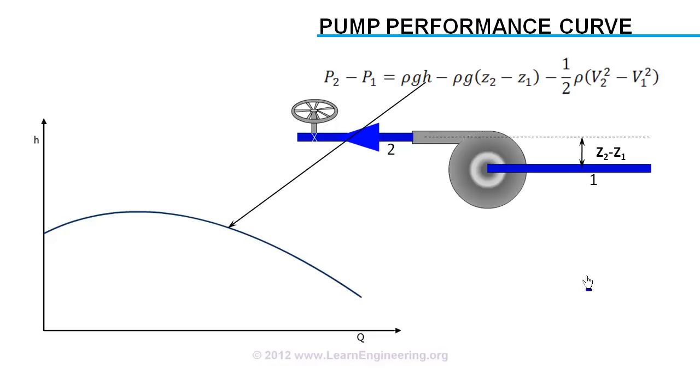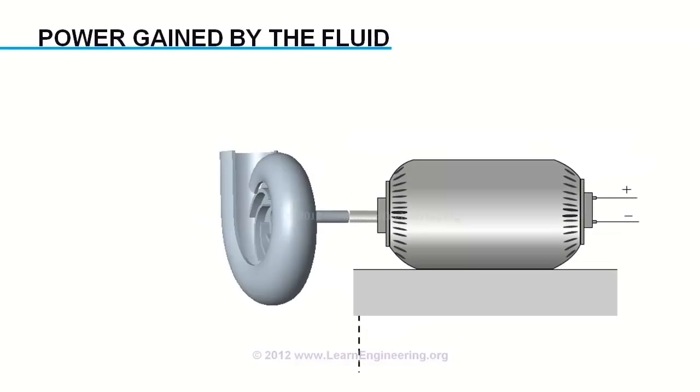Now, we will see how much power fluid is gaining from pump power input, or shaft power. Power gained by the fluid will be lower than the power supplied. One main factor is hydraulic loss, as we discussed. Other factors are volumetric loss and mechanical loss.